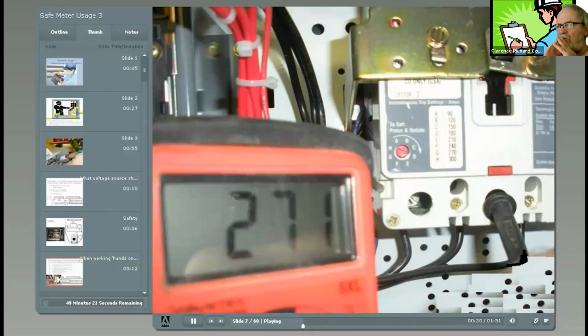It does not mean that a faulty breaker disconnect properly disconnected all three phases from the load side of the breaker. A breaker disconnect's contacts sometimes weld to the breaker disconnect's terminals when overworked, shorted to ground or another phase. The breaker disconnect lever or toggle lever may appear to work normally externally, but may not be working right internally.